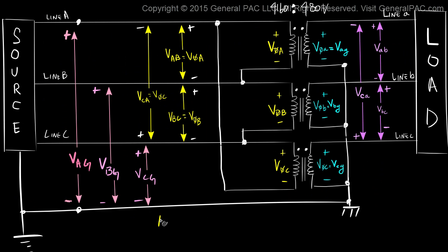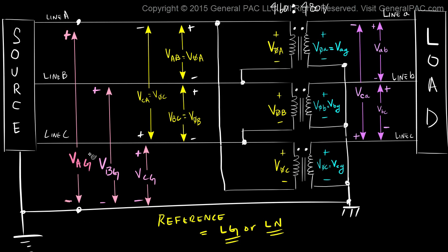In general terms, this reference quantity is always defined as a line-to-ground quantity or a line-to-neutral quantity. On the high voltage side — which is the delta side — VAG, VBG, and VCG are our reference quantities. For the sake of simplicity, we use VAG as our reference quantity on the high voltage side.